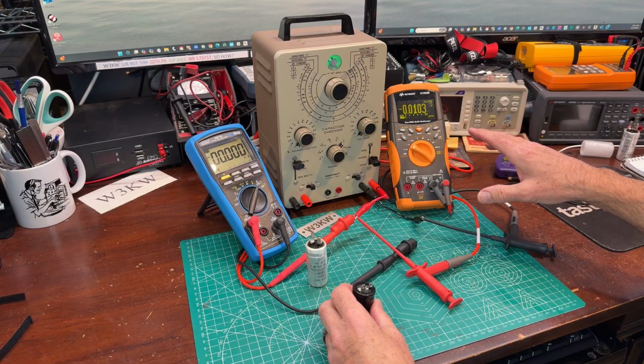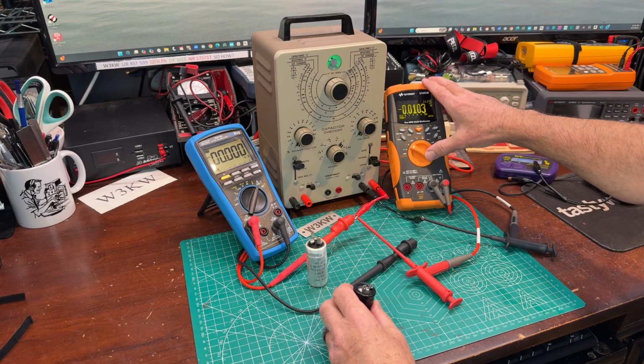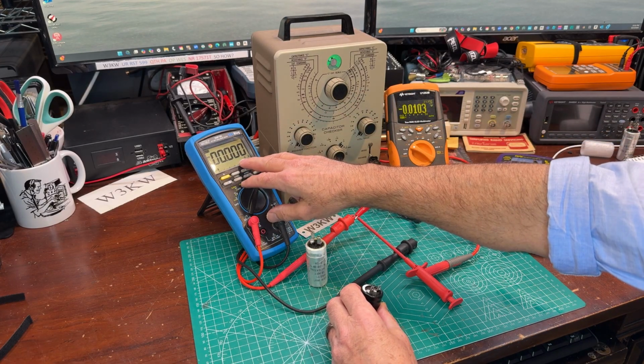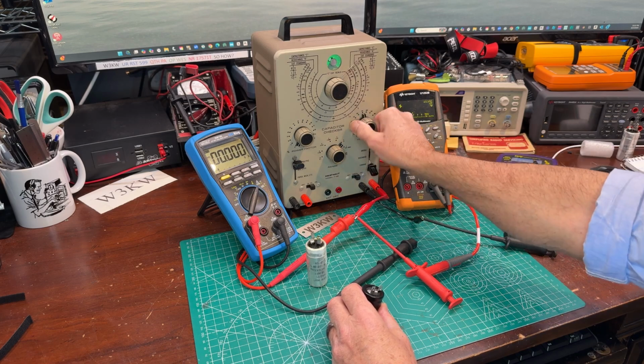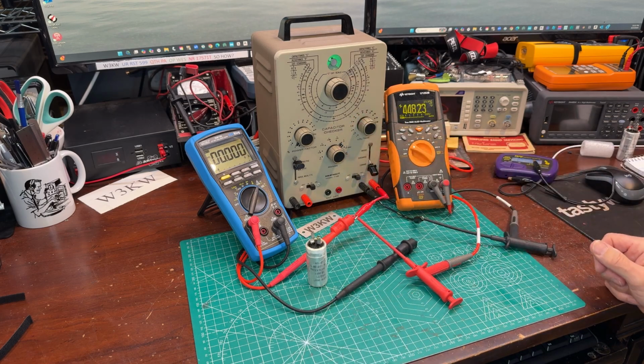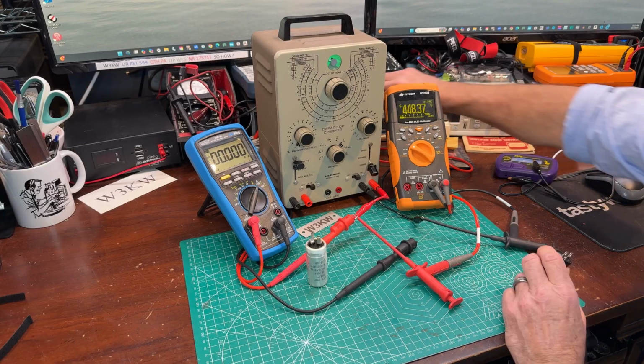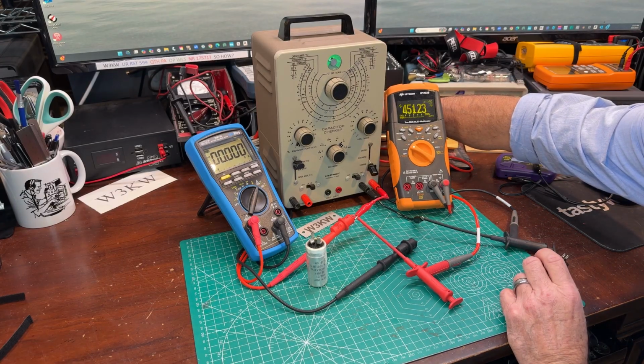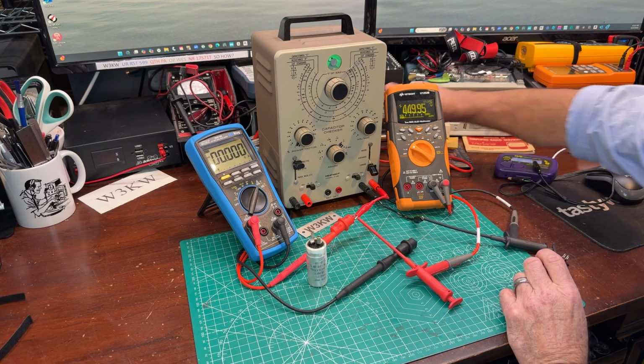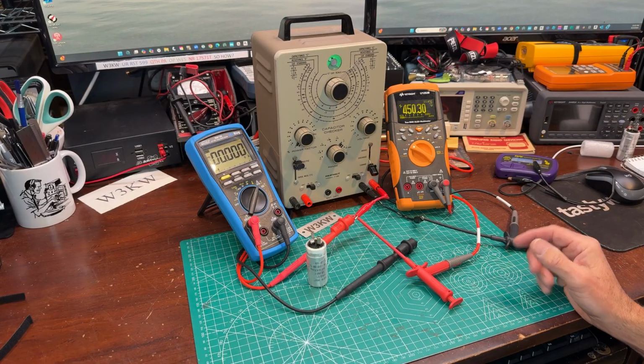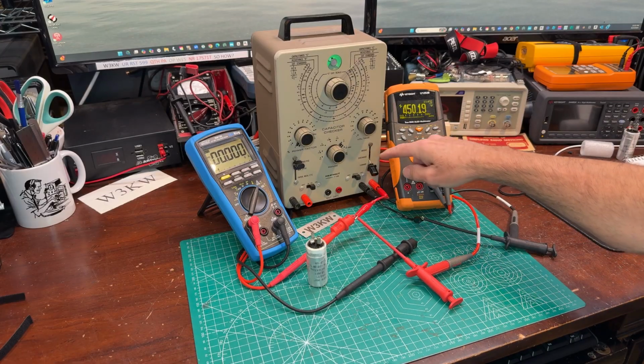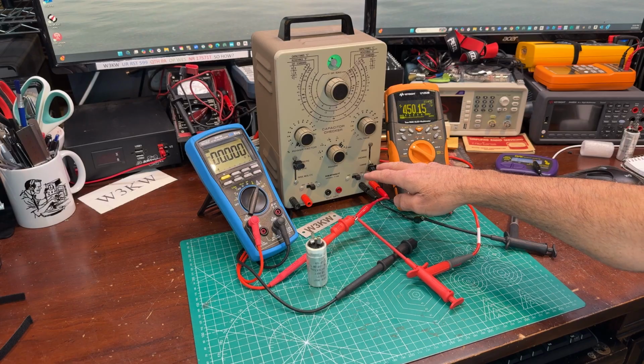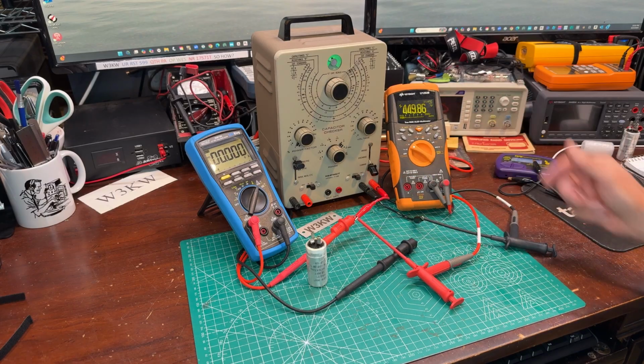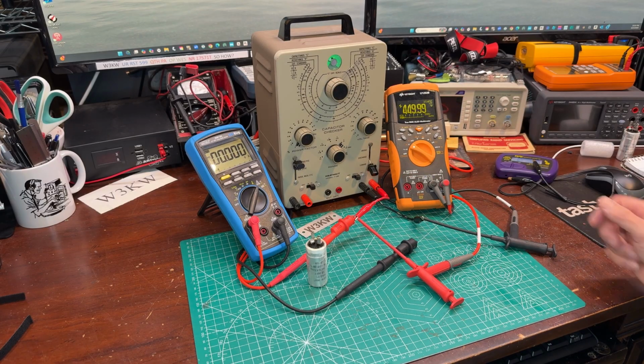I've got this test set up here. This is reading voltage, this is reading amperage. So let's go to leakage and bring the voltage up to 450. Now I'm only showing you that we have about 450 volts, and I can adjust it using a variac here for the input voltage, which in this unit is just below line voltage. There's 450 volts, no load. We're just coming out of the IT28 and going right into the voltmeter. So there's our unloaded 450 volts.